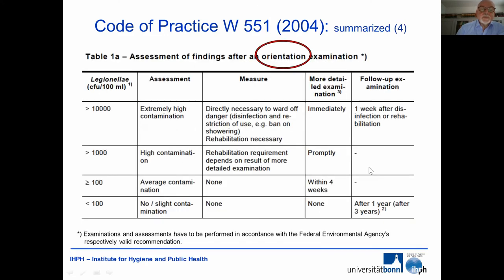Then we have the assessment: what do you have to do if you have Legionella in your system? It's important to note if you have a systemic contamination, meaning also in the central part. If the concentrations are below 100, you have nothing to do, and you should re-monitor after one year, or without hospitals after three years if there are no significant alterations.